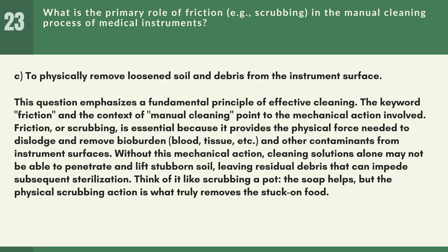Without this mechanical action, cleaning solutions alone may not be able to penetrate and lift stubborn soil, leaving residual debris that can impede subsequent sterilization. Think of it like scrubbing a pot. The soap helps, but the physical scrubbing action is what truly removes the stuck-on food.